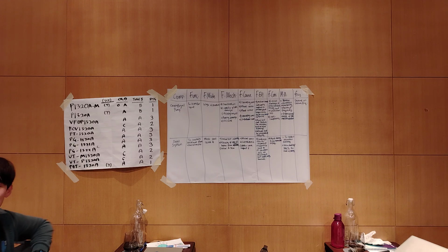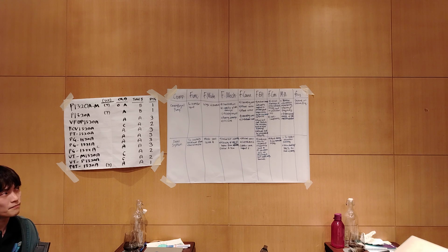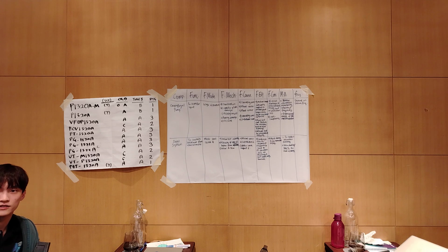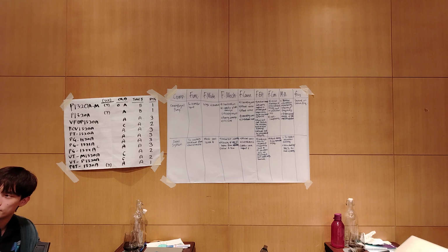Question. For your mitigation number 2, enforcement or revision of PM implementation, the interval, how do you put it into the task list and recipe and so on? Desmond, can you help? The mitigation assumes that we have the plan already. Number one, you can do vibration monitoring, which we would schedule, for example, when the tank or process is shut down for mechanical maintenance.